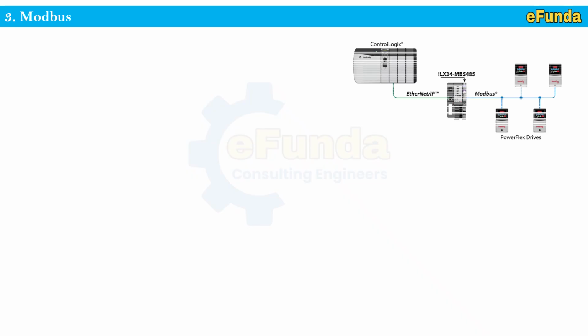Third is Modbus. One can refer to the picture where ControlLogix is connected through the Ethernet IP to the Modbus, and then further the same is connected to the PowerFlex drives with the help of Modbus communication. This is how the controllers are being connected to the main controller for communication.